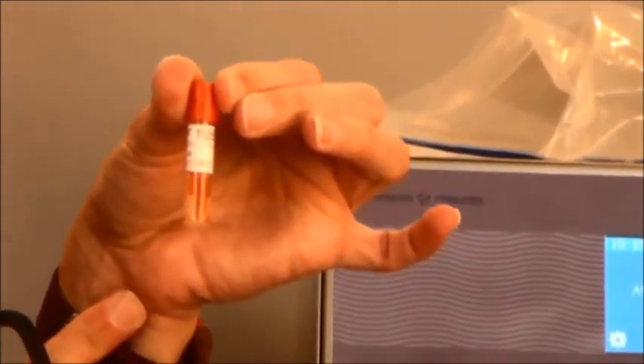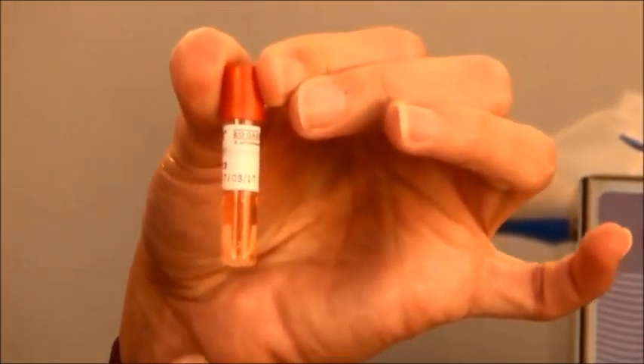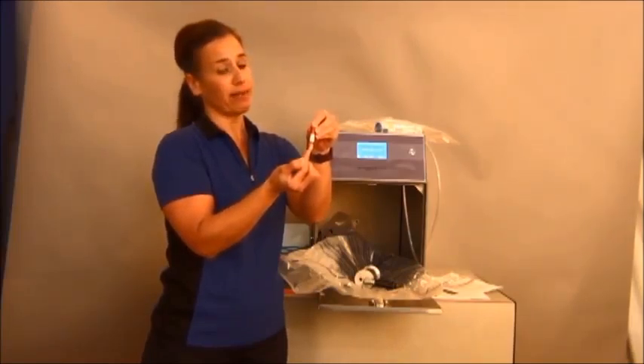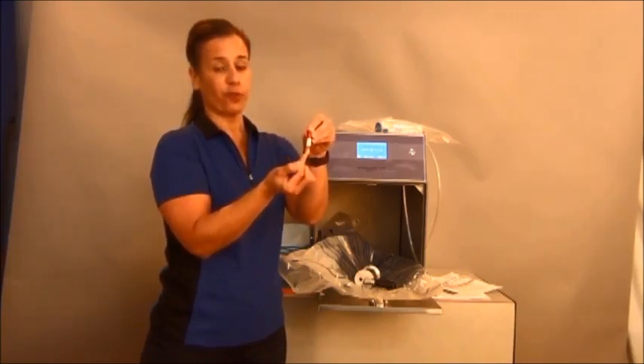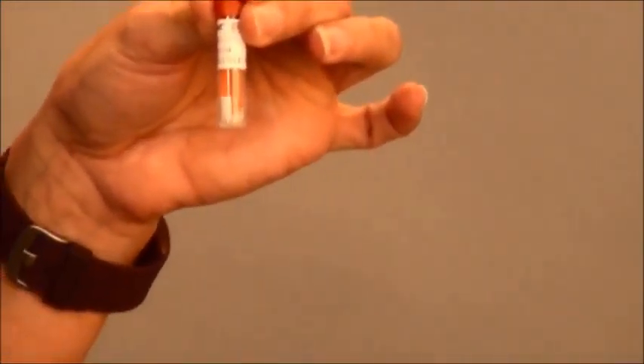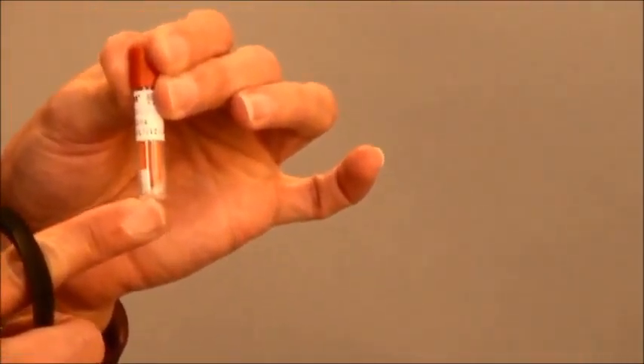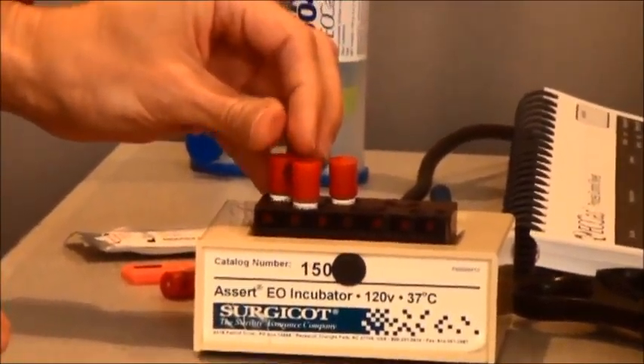You want to shake your BI to make sure that that spore strip is totally saturated with your culture media. It does need to be incubated at 37 degrees C for 48 hours. You also need to utilize your controller, a biological indicator that has not been run through a sterilization cycle, so you know that the bacteria on this spore strip are still viable. You activate it in the same fashion. Make sure you mark this as the controller. Also incubating it for 48 hours.